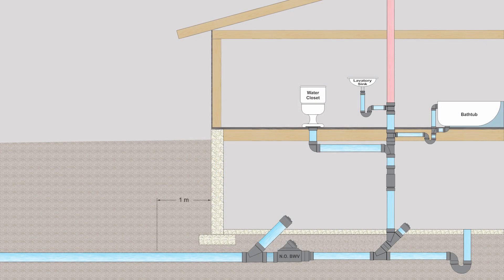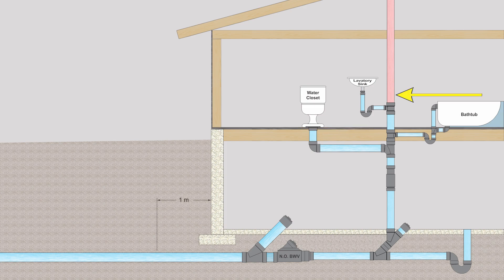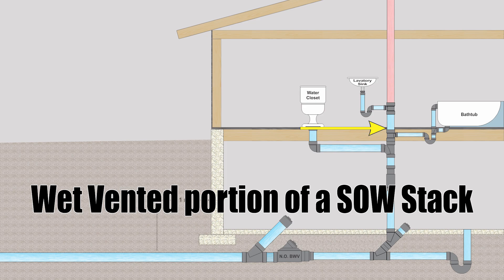In this next diagram we have a slightly different arrangement. We've got a lav sink, a bathtub, and a water closet, but they're tied into a soil waste stack. The lav sink has its own vent, but the bathtub and water closet will need to be wet vented through the soil waste stack. We call that a wet vented portion of a soil waste stack, from this point right down to the water closet trap arm connection.